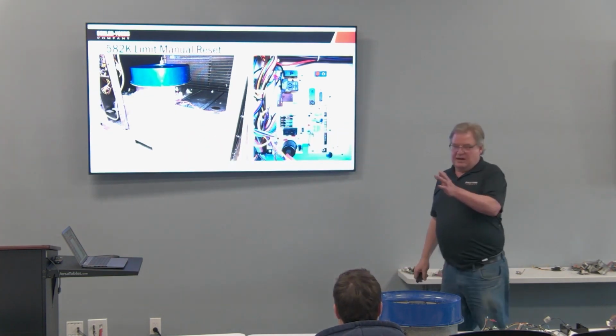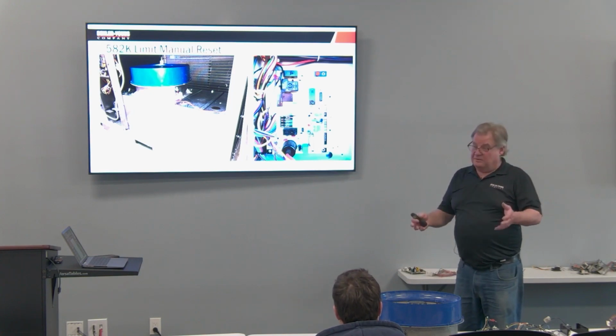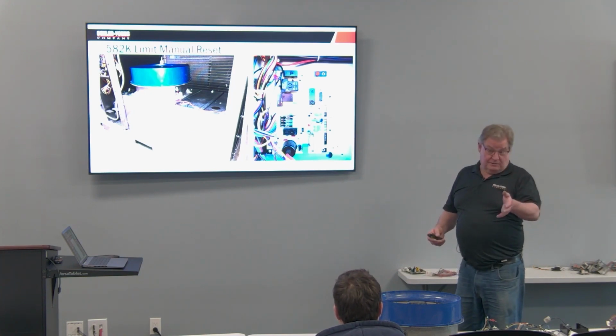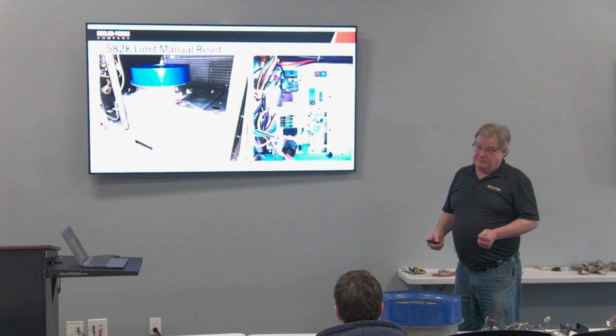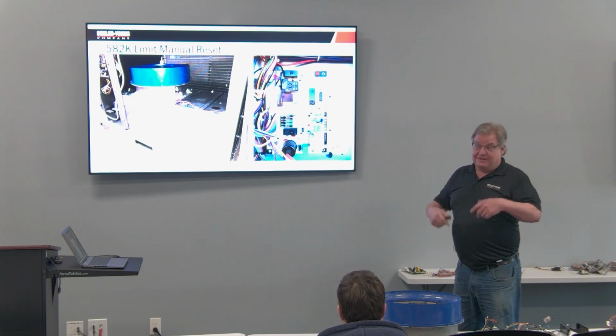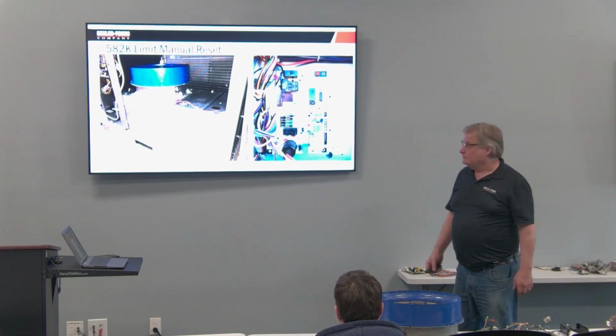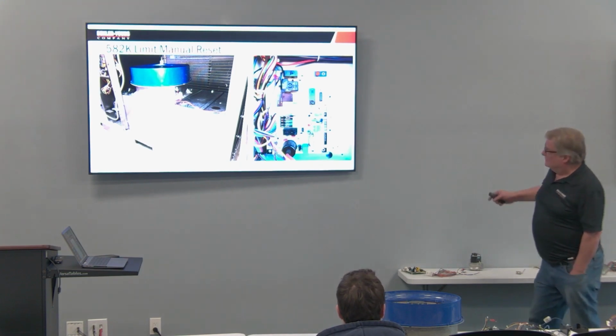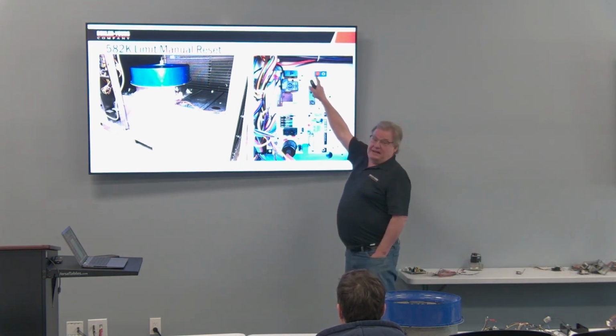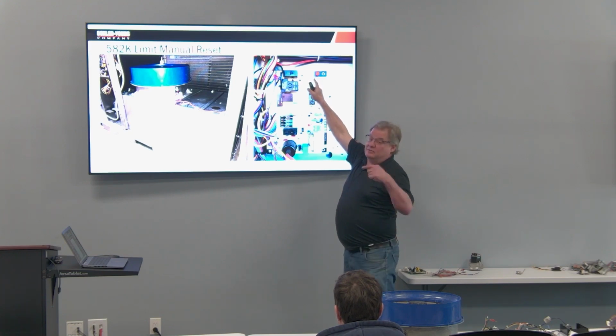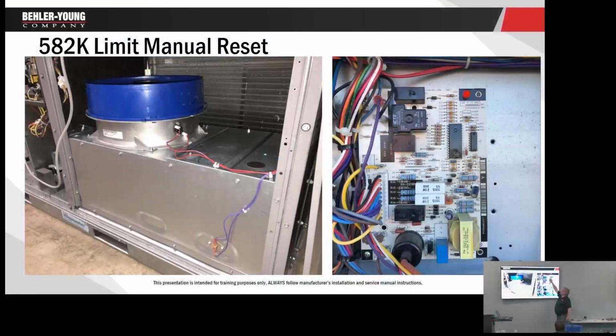Okay, but just know if you got one of the older units and you got no 24 volts and you got a 2020 or earlier, go look, see if you got the manual reset limit. Reset it, figure out why it tripped. Okay, but they eliminated it. This red light on here, okay, if you have power coming through the smoke jumpers, through that safety circuit, that light will be on. If that light is not on, I've got a blown fuse on the board, or that safety circuit's open, or a smoke detector's open.